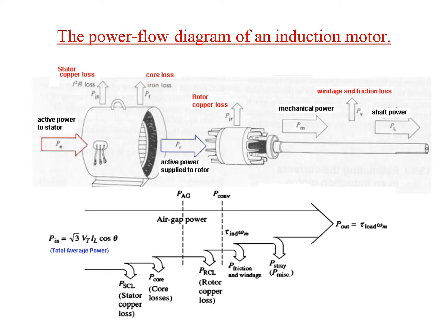After these two losses, whatever is available is the air gap power inside the stator. The air gap power is applied to the rotor, which undergoes the rotor copper losses. The power available at the output of the rotor is called the power converted — where electrical power is converted into mechanical power. It further undergoes windage and friction loss and stray power loss, and then becomes the output power available at the shaft.